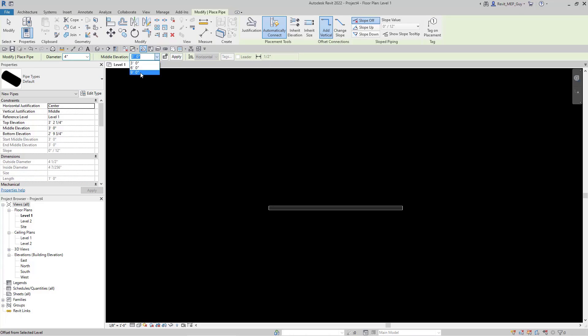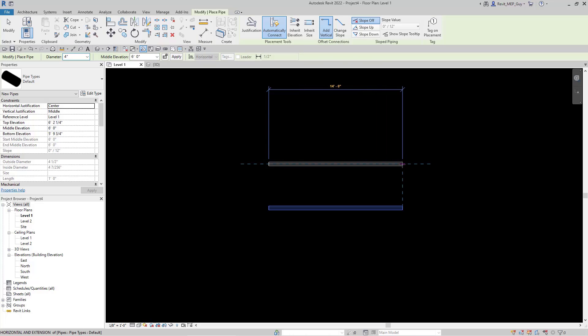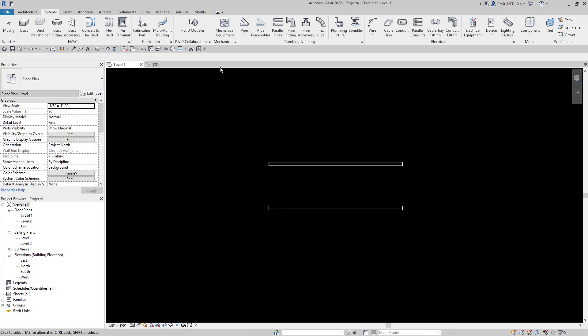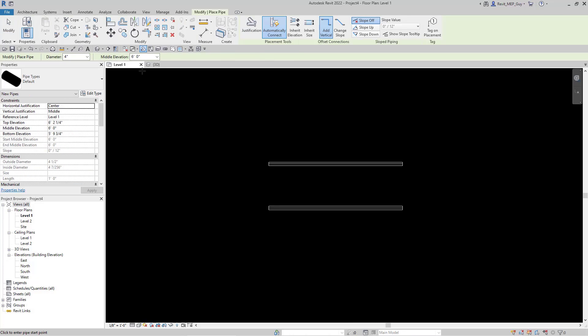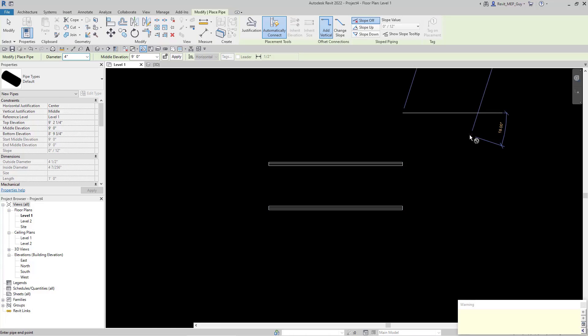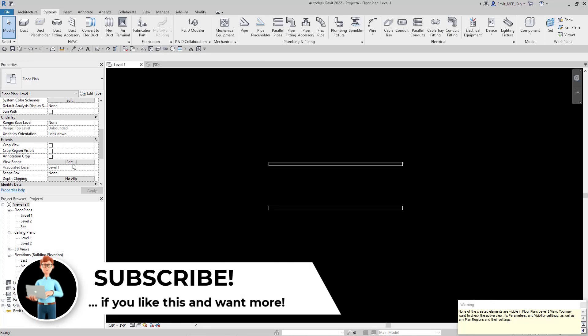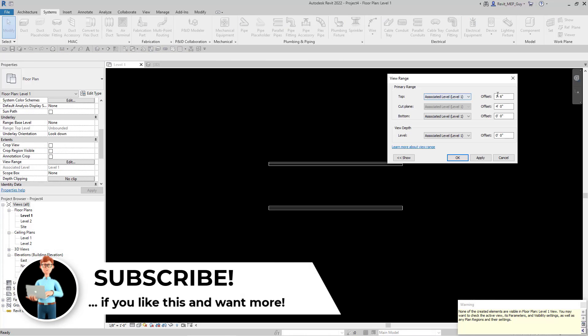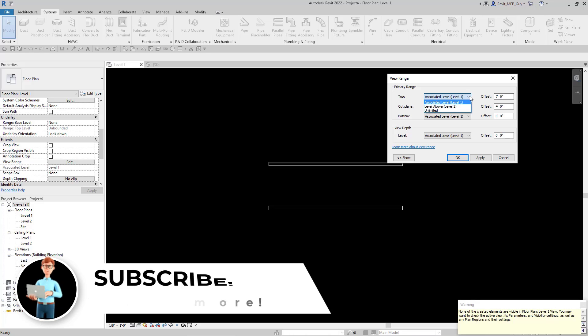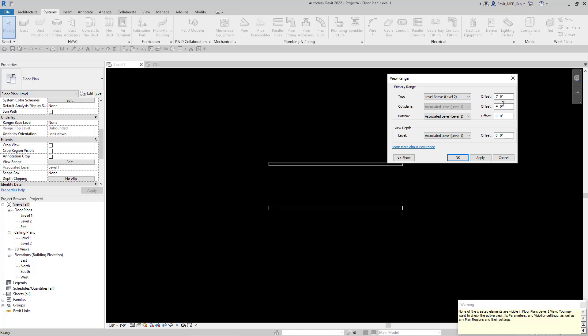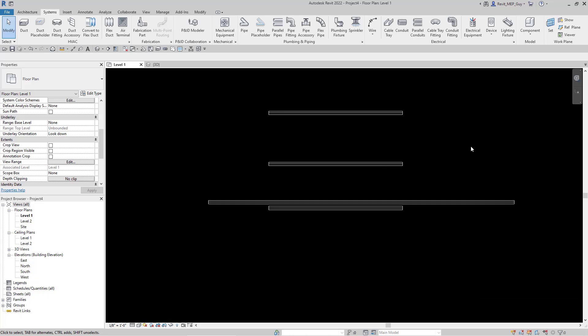So this time I'm going to draw it at nine feet, or let's say six feet, and everything is working now. Let's try drawing the pipe at nine feet and see what happens — and as you can see, we're not able to draw this pipe. So let's go back to our View Range settings, hit Edit, and my top is still set at seven foot six. I want the top of this view to be at the next level — Level 2 — so I'll set it to Level Above, Level 2, offset zero. Now all my pipe starts to show up.